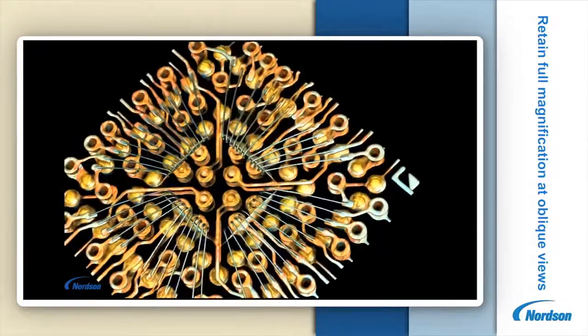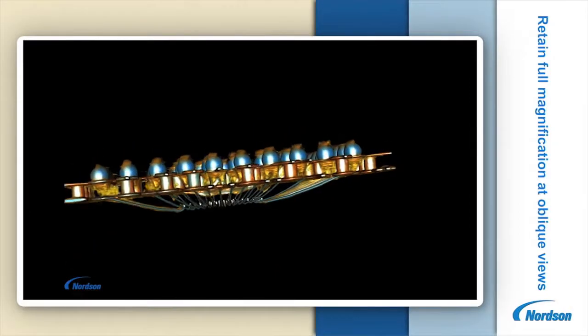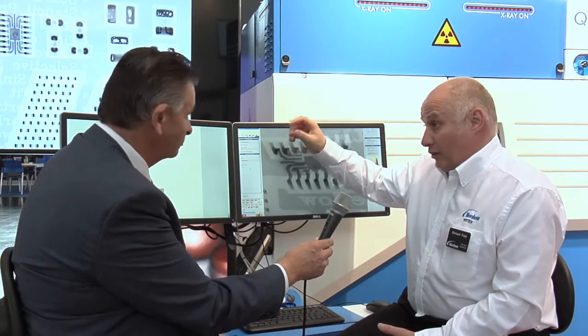It's incredible. I'm noticing from some of the images we're seeing behind us that you're not just seeing voiding information, but you're seeing a lot of detail coming out from defects and little pockets in the laminate itself. Yeah, that's a difficult thing. Here, for example, is a €5 note, just a piece of paper, very difficult to image on an X-ray system, but the ability of this system to pull out contrast from an image is clearly shown there. It's a difficult subject, but you can see all the detail on there. And furthermore, in some of these images, we've got 20 micron bond wires, and we've got fairly thin laminate and photoresist, which you can also see all in the same screenshot. So a very versatile system.